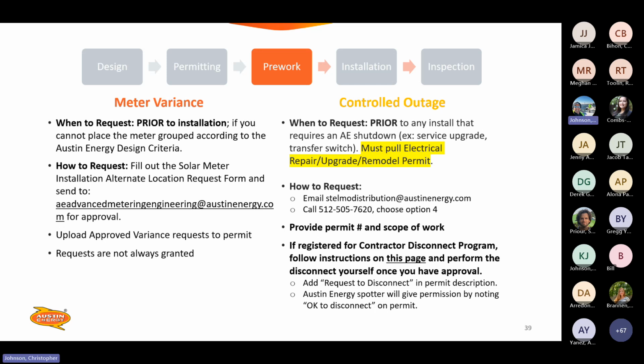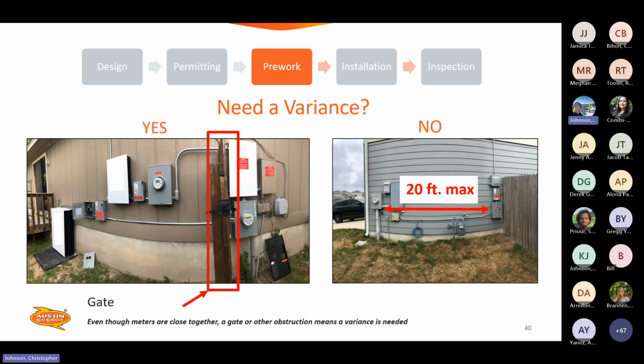A controlled outage must be requested prior to any installation that requires a shutdown, service upgrade, transfer switch. You must pull that electrical permit, whether it is a repair to fix something, an upgrade, or a remodel permit. You have to have that active permit in order to email or call St. Elmo Distribution at austinenergy.com, or you can call them at 505-7620, choose option 4, but you have to have that active permit number and your scope of work ready. If registered for the CDP, the Contractor Disconnect Program, follow the instructions on this link and perform the disconnect yourself once you have the approval, but you have to be part of that CDP program. If you just think you're going to cut the seal and get forgiveness, there's usually an $800 fee tacked onto that. And we do have to turn people in for that as we see them.